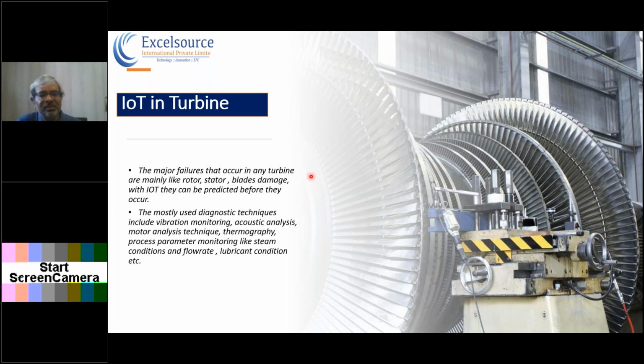So tribology is something which can be installed in the lubrication systems to maintain lubrication conditions. It will maintain the specific viscosities. It will monitor how conditions are changing in the lubrication system, and it will alert us in time if there is any mixing of water into the lubrication system, which could otherwise lead to a big disaster or failure at the top of the turbine.